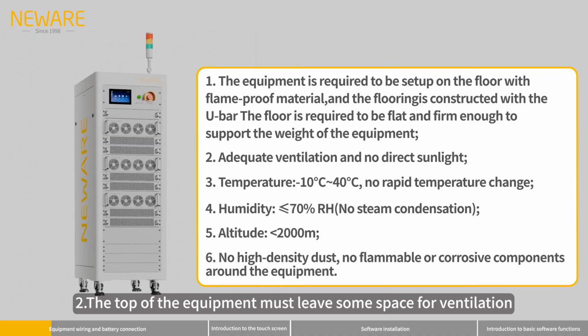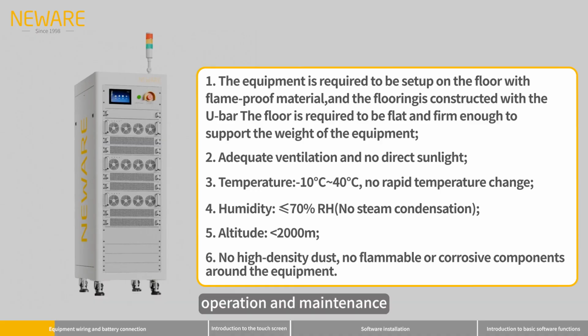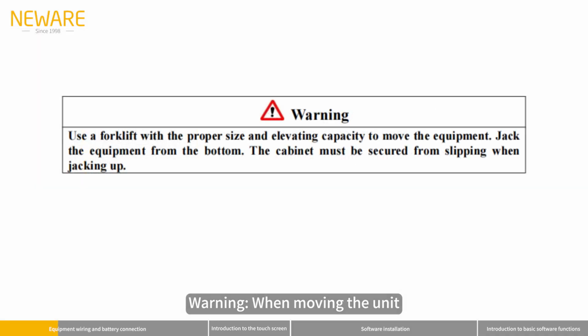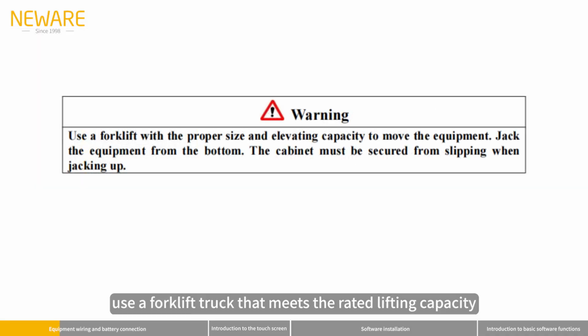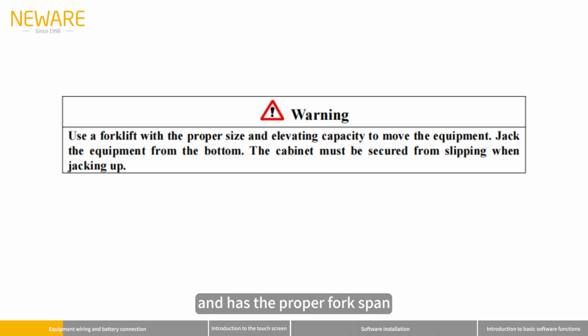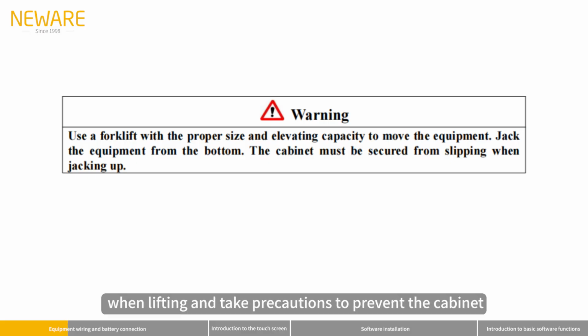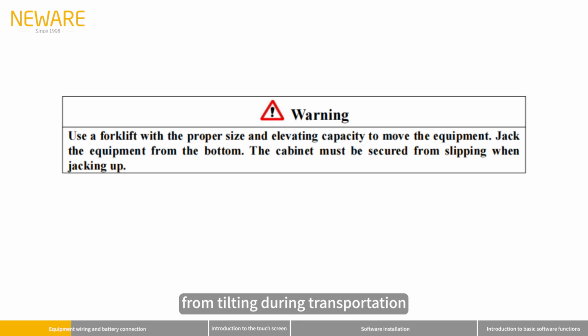2. The top of the equipment must leave some space for ventilation, operation and maintenance, usually not less than 500 mm. Warning: when moving the unit, use a forklift truck that meets the rated lifting capacity and has the proper fork span. The cabinet must be lifted from the bottom. Support the cabinet from all 4 sides when lifting and take precautions to prevent the cabinet from tilting during transportation.